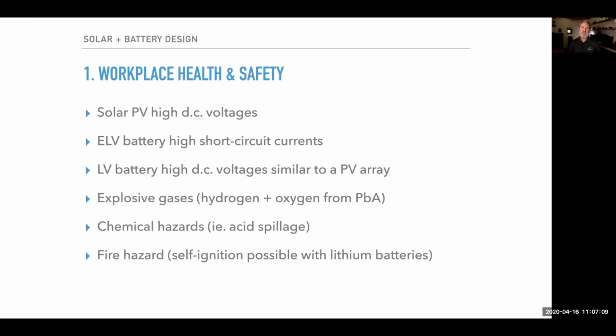Some battery systems have combustible gases being emitted under normal operation, particularly, for example, lead-acid batteries. When they charge, they'll evolve hydrogen and oxygen at the cathode and anode, and that makes a very explosive mixture. So it's a requirement to maintain ventilation. There are standards that cover those ventilation requirements. We've also got chemical hazards. In the case of a lead-acid battery, it's an acid. It's a relatively mild acid, but you don't want to get it in your eyes. But other chemistries may have more toxic materials as well. Some might emit gases which are poisonous to breathe in, for instance. So you need to consider those in the design of a system.